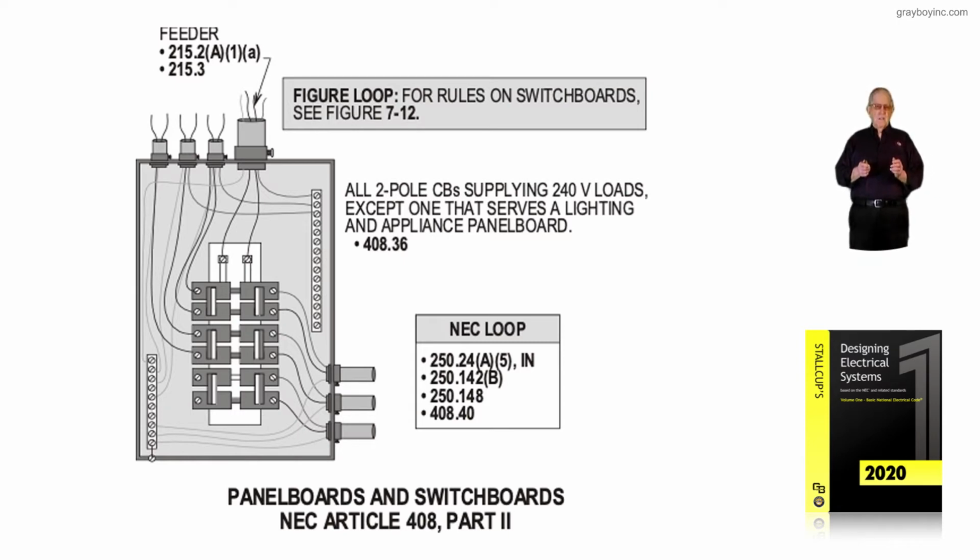Now notice the feeder coming in is designed and the load calculated in accordance with 215.2(A)(1)(a), where there's not any kind of a correction factor or adjustment factor involved. Then we would use just our 215.2(A)(1)(a).